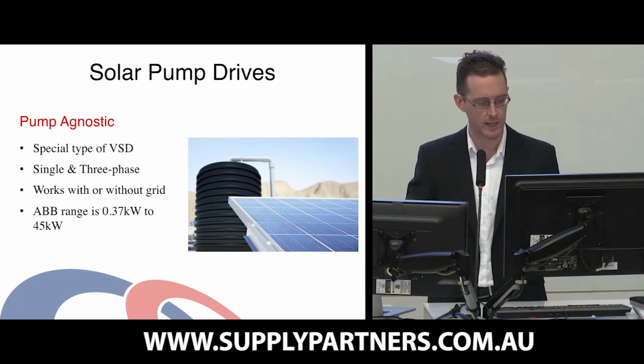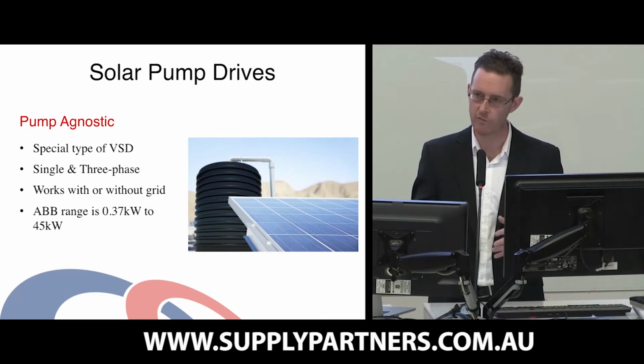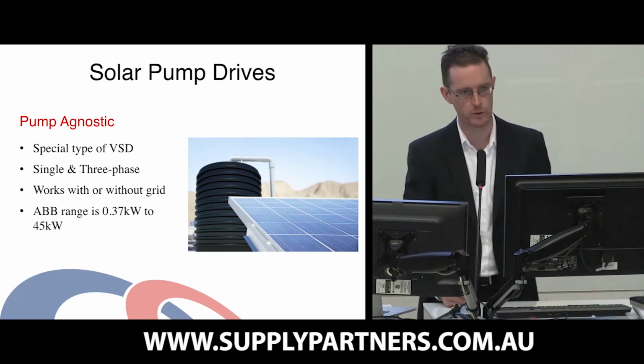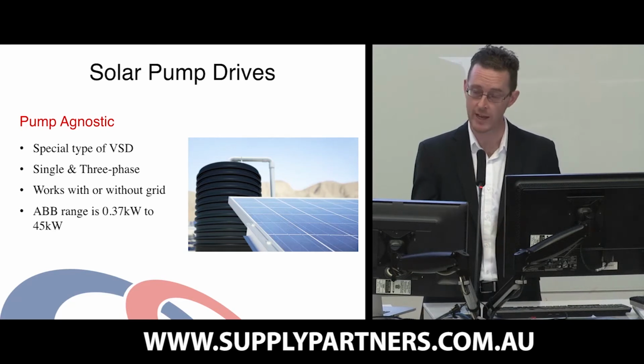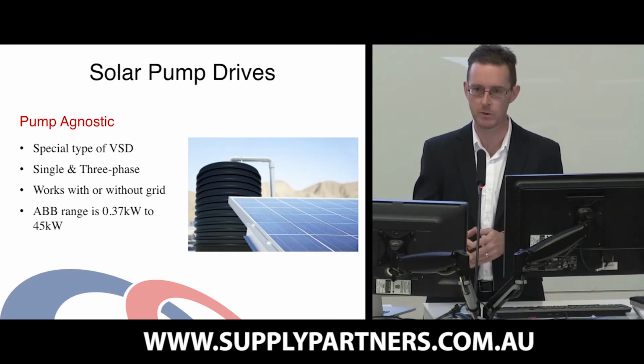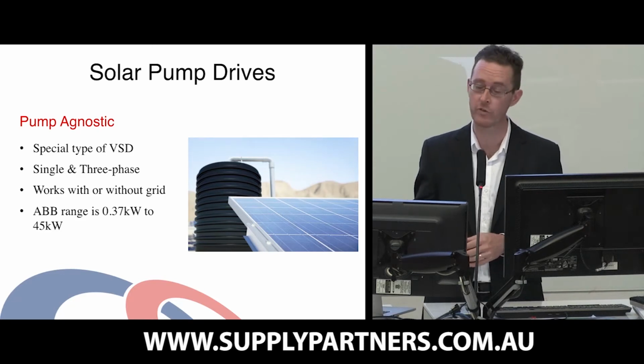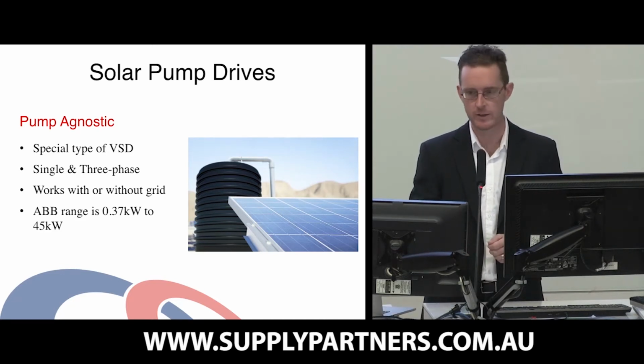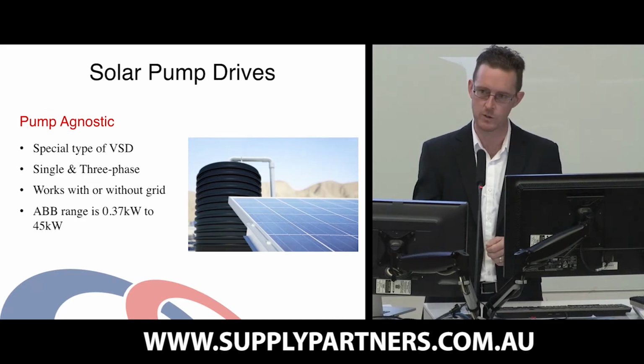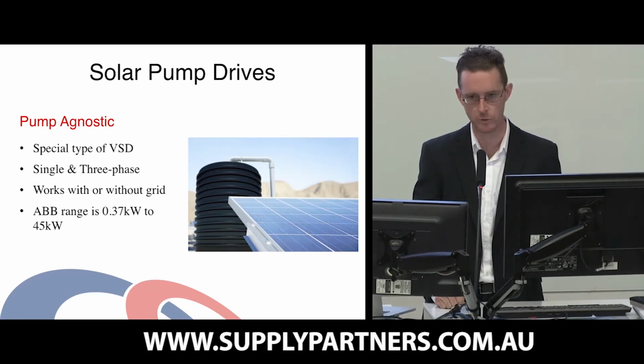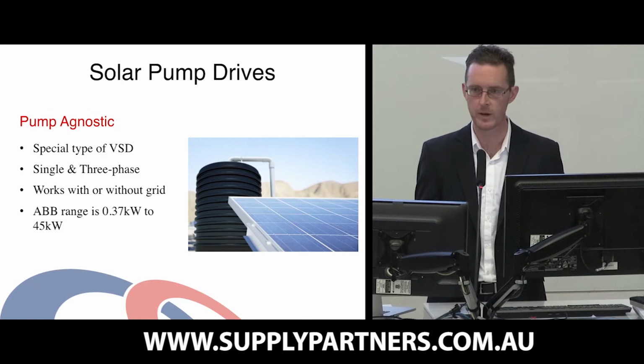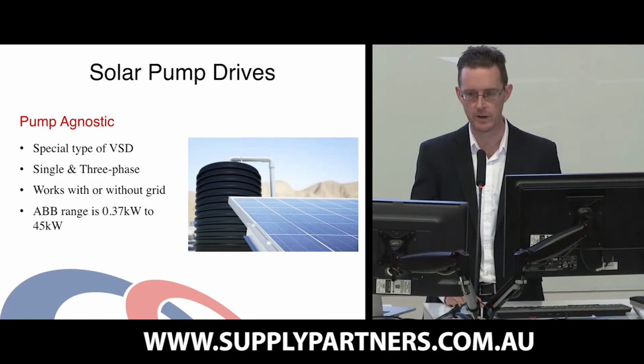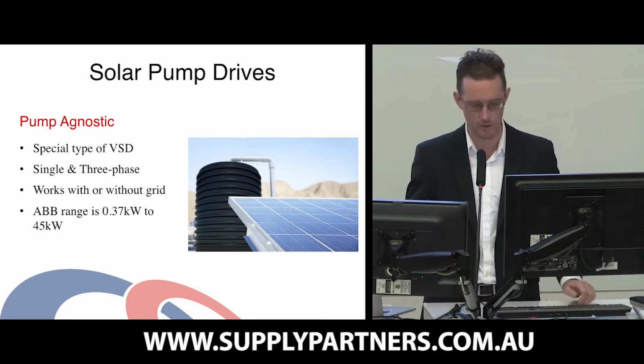And so these drives can be run either in conjunction with the grid or off-grid. So when they are run in conjunction with the grid, there's a changeover switch. You can't run the grid and the solar together like you might think a typical solar inverter works. Instead, this is a case where you select the switch to be solar only and it's running off the solar. You change the switch over to grid and it runs off the grid. Obviously, you can automate that whole process, but it does mean that we can run both during the day and during the night. In the case where there's no grid available, then we just run off-grid effectively straight off the solar.